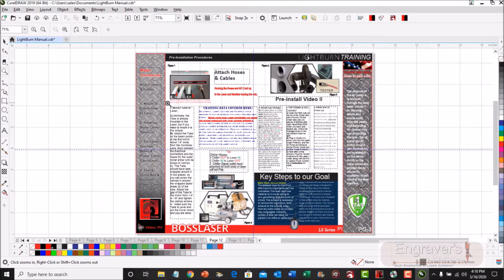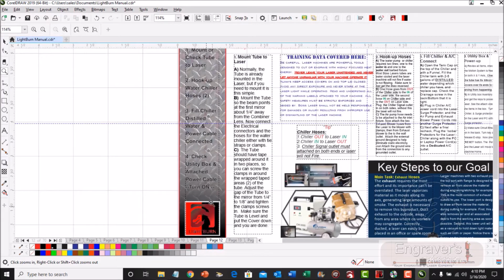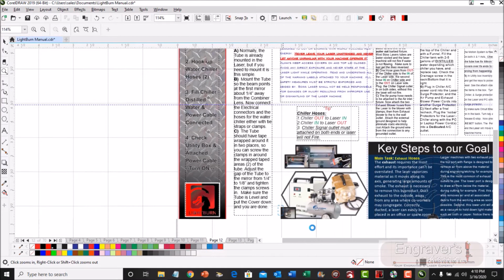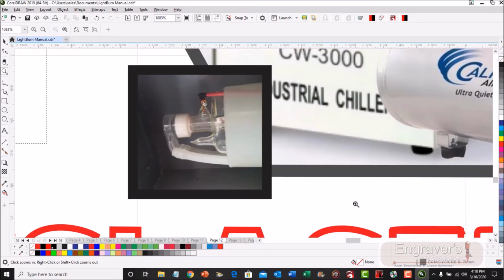So next, once you do that, you're going to start in first. I should have said before that, you're going to inspect the tube. So you open up the back cover, top back cover of the unit, and look at the tube. The new tubes, the connector is directly to the tube. There is a screw on there with a red cap. All you're going to do is look and inspect the tube. You're not going to take anything apart unless you have to. And if you do, you're going to have me on the phone or customer service on the phone.